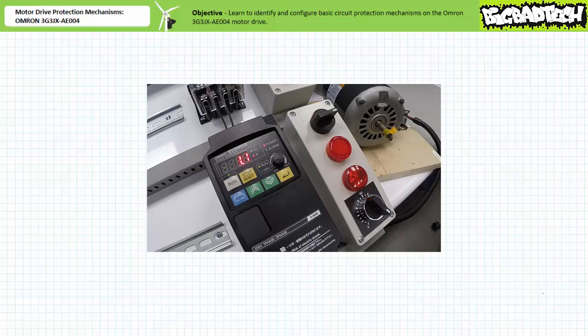Obviously an overload warning of 1.1 amps is way too low given this motor is unloaded. However, a technician can change the overload warning level and enable this function to get an early notice of a potential overload and take the necessary precautions. Let's return communication parameter C041 overload warning level back to the default state of 2.6 amps so we won't get a false warning of an impending overload.